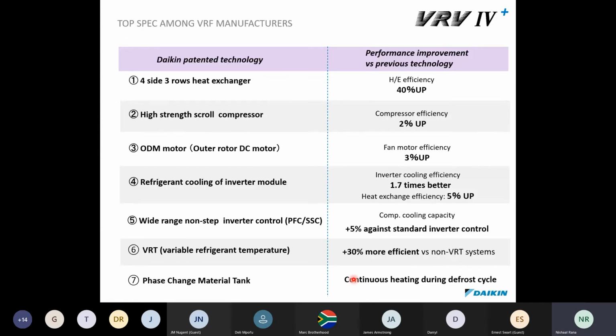So, summary of the thing, we basically have a 4-side 3-row heat exchanger, which has increased our efficiency by up to 40%. High strength scroll compressor, which has given us 2% extra efficiency, right? Your DC fan motor efficiency, 3%. Your refrigerant cooling of the inverter module, right? It's 1.7 times better, which increases the heat exchange efficiency by about 5%. The wide range of the non-step inverter control, right? Your compressor cooling capacity plus 5% against a standard inverter control.